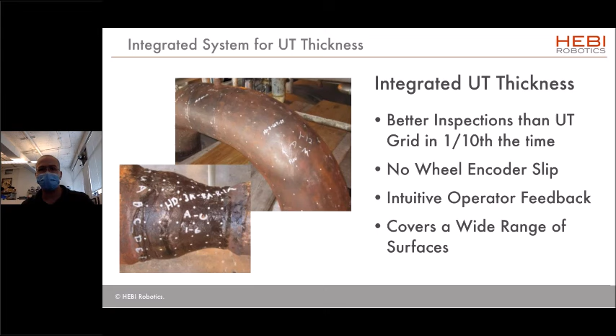So instead of putting out that grid of points, what you'll get is a 3D thickness map, a C-scan of the data. Aside from being more intuitive, a key thing that you get when you marry the thickness data with the 3D information is that it allows you to automatically align and compare scans over time. If you come back and need to do a scan, whether it's a week later or 5 years later, right now, at worst, you're just taking 2 numbers in a spreadsheet and seeing how they change, really not knowing what went into those numbers. At best, you might have scans that are flat and you're trying to marry them manually, and there might be some guesswork there. With the 3D data, it automates that and provides a lot more confidence.